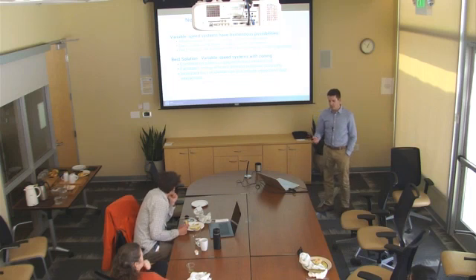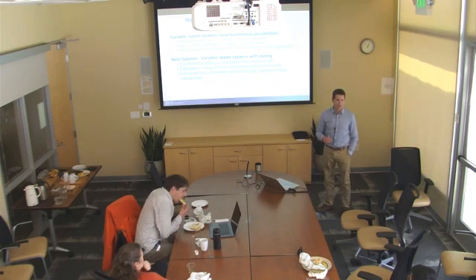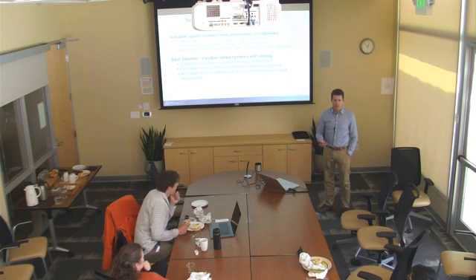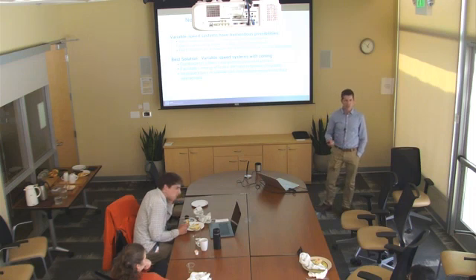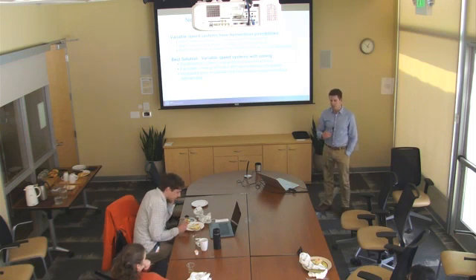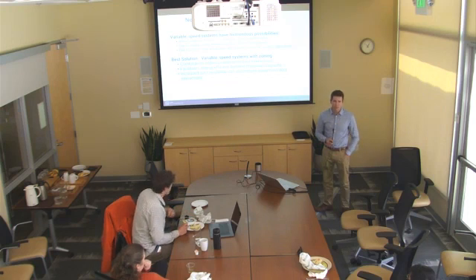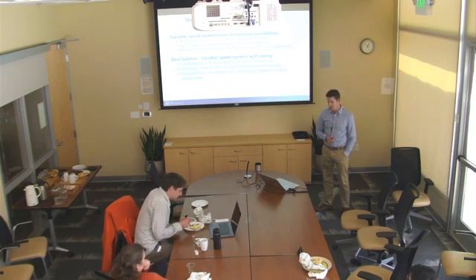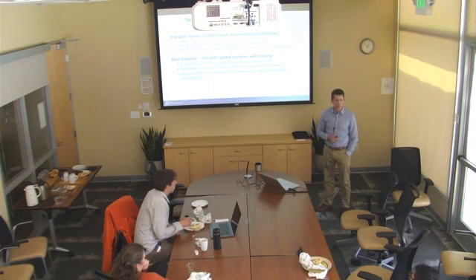Obviously, we showed that you would get a big performance hit if you do that during a demand response when your attic is warm. We were just talking about the peak demand is in the afternoon. Your attic maintains that heat throughout the evening hours. So by including zoning, you can have a demand response and maintain efficiency. And then lastly, we showed that increasing duct insulation will also improve variable capacity performance. And will also reduce those interactions with the attic. That's what I got. Are there any questions?